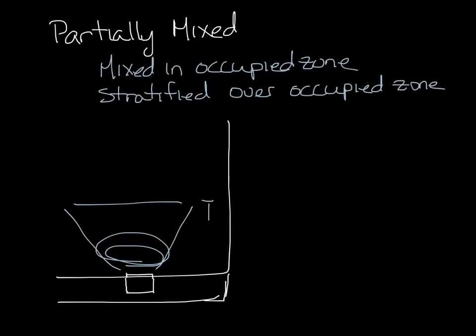The air comes out swirling and it has a throw of about four to five feet. The air is rapidly swirling out of the face, which induces room air into the supply air and creates a mixed space up to that five foot range.